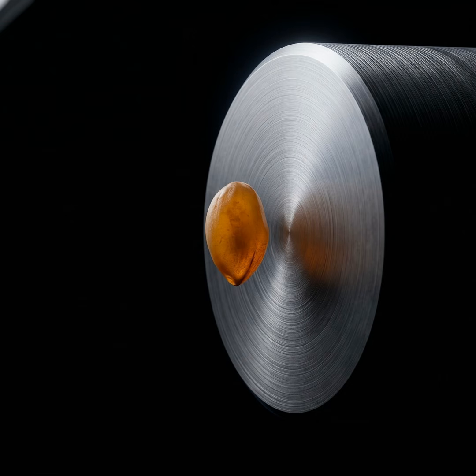It pulls more juice. Exactly. An automated system monitors that baseline current. It can predict a catastrophic bearing failure days in advance simply by spotting a steady, abnormal spike in power consumption on a specific motor. That is brilliant. The physics of the failing metal translates into electrical data, which translates into a text message warning the operator. It's all just data flow.